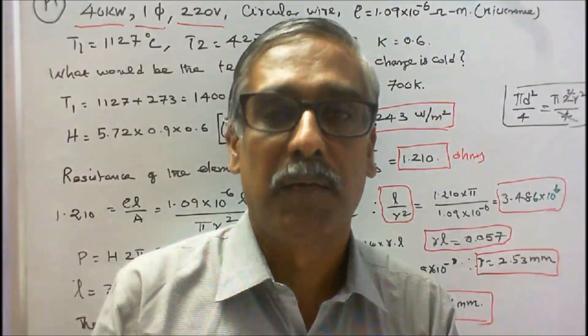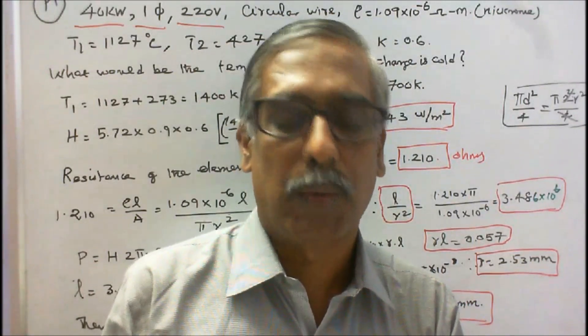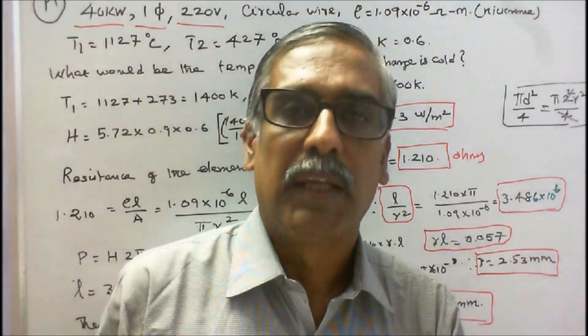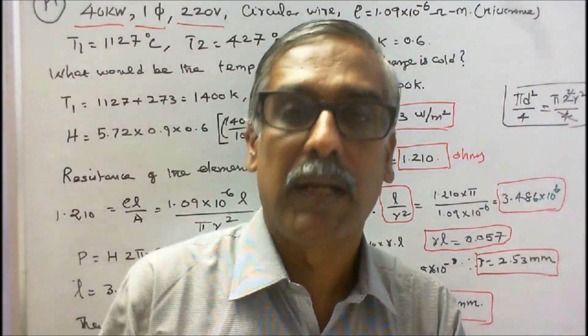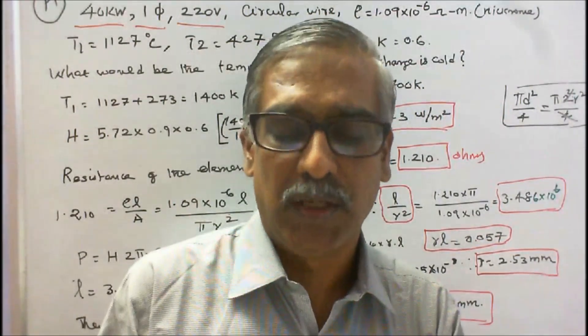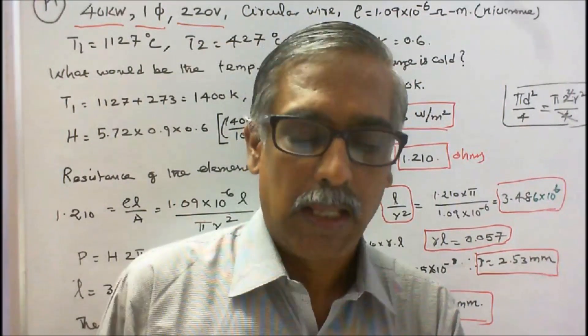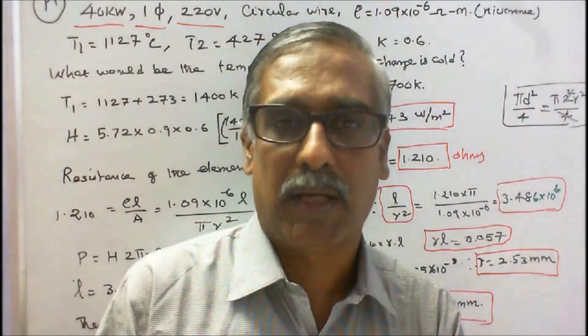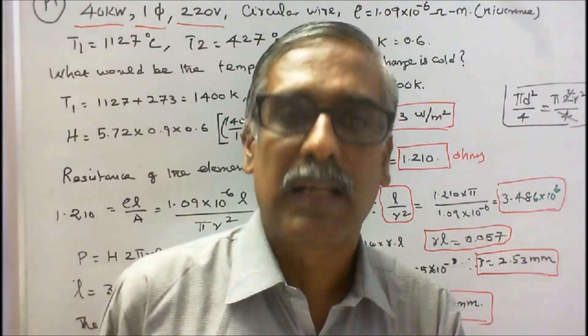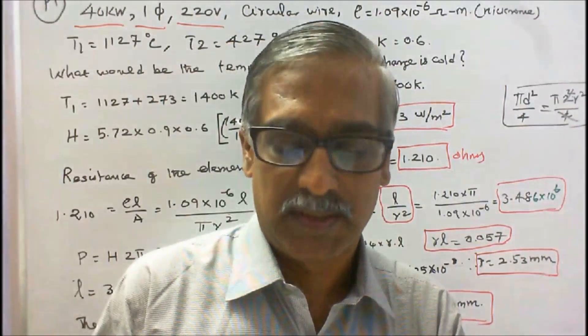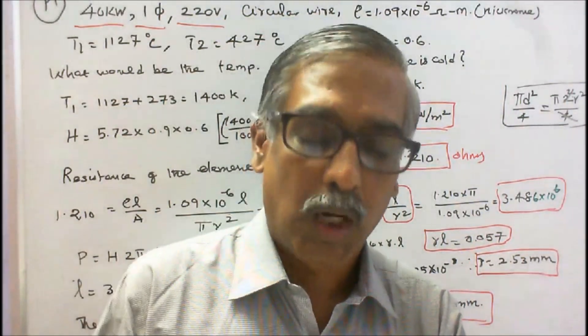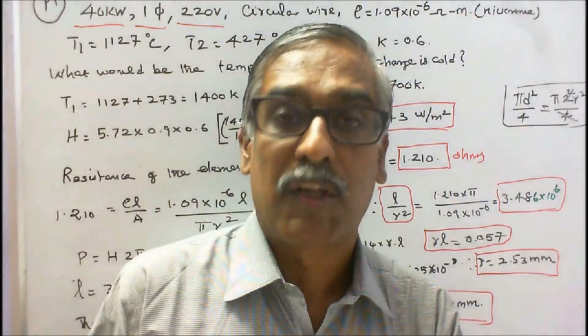A 40kW single-phase 220V resistance oven employs circular nichrome wire for its heating element. If the wire temperature is not to exceed 1127°C and the temperature of the charge is to be 427°C, calculate the size and length of the wire required. Assume emissivity is 0.9, radiation efficiency is 0.6, and resistivity of the wire is 1.09×10⁻⁶ ohm-meter. What would be the temperature of the wire when the charge is cold?